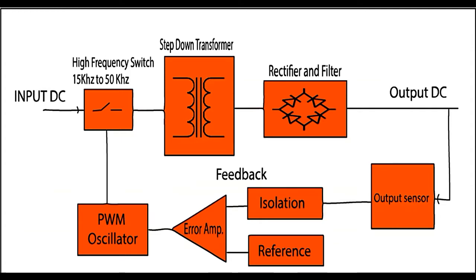The rectified output gives DC. That output DC goes through a sampling process using an output sensor. There is also an isolation reference error amplifier for feedback, and a high-frequency switch operating at 15 kHz to 50 kHz. The switching is performed by a PWM oscillator, forming a closed loop.